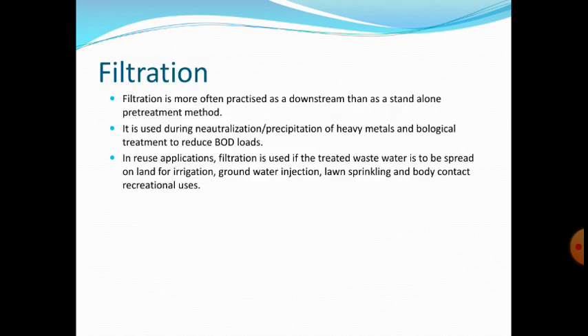Next comes filtration. Filtration of industrial wastewater is more often practiced downstream of other pre-treatment processes than as a standalone pre-treatment method. It is used during neutralization or precipitation of heavy metals and biological treatment to reduce biological oxygen demand loads. It may also be used to remove lime precipitates or phosphates, and as a pre-treatment before discharge to an activated carbon column, or to a dialysis or reverse osmosis unit.